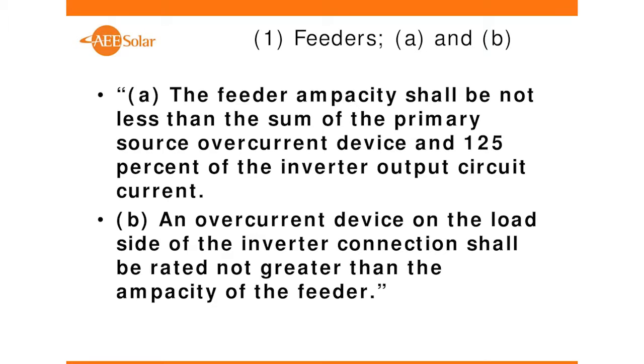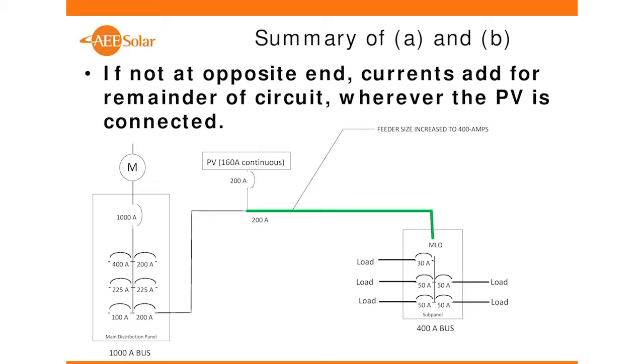Feeder ampacity should not be less than the sum of the primary source breaker and 125% of the inverter output circuit current if you're feeding it from one end. Okay? Secondly, we can put an overcurrent device on the load side of the inverter connection, and it shall be rated for not greater than the ampacity of the feeder. So what we do here is, okay, now let's move that PV system from here to the middle. There's nothing wrong in here for the 200 amps. No more than 200 amps can flow in this part of the circuit right here, right? Everybody clear with that?